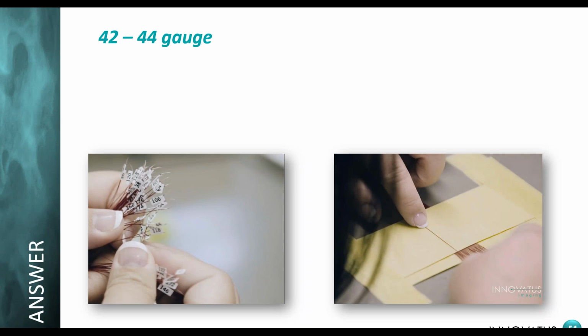These wires always have to be soldered by hand. When we put a new cable on a probe, think of a coaxial cable: there's insulation, shielding, and a center conductor smaller than the width of a human hair. We have to solder the shield and the conductor, doing that 128 times on the probe end and 128 times on the connector end, all done by hand.